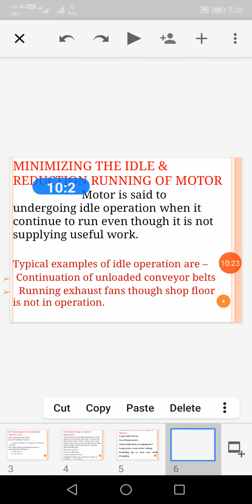Some examples are given here. The running of a cooling tower fan though ambient conditions are favorable. Operation of an air conditioning unit even when the desired temperature is achieved, and air conditioning running with the window open. Stopping these motors is a simple way to achieve large savings of energy as well as money. You reduce your energy bill by stopping this machine, stopping this motor at the redundant time. Manually or automatically switching off idle or redundantly operating motors is the ultimate solution to avoid energy loss.